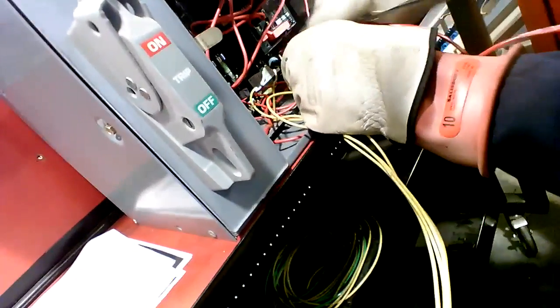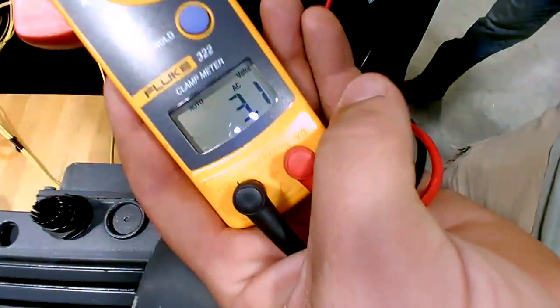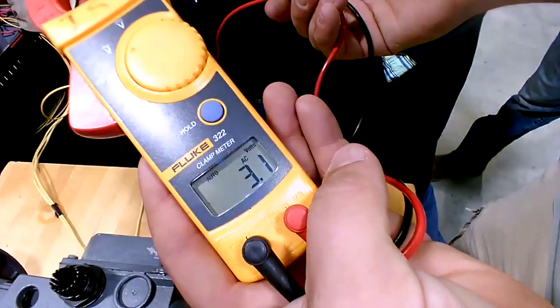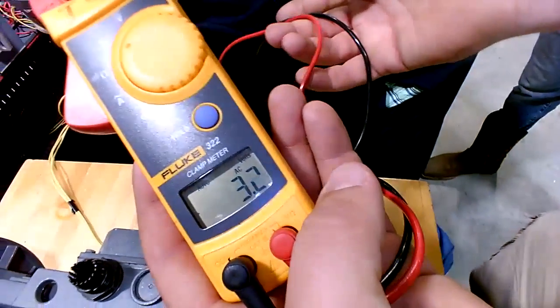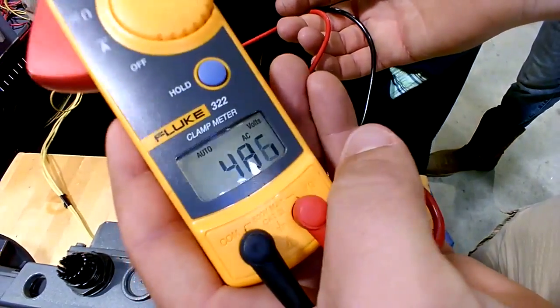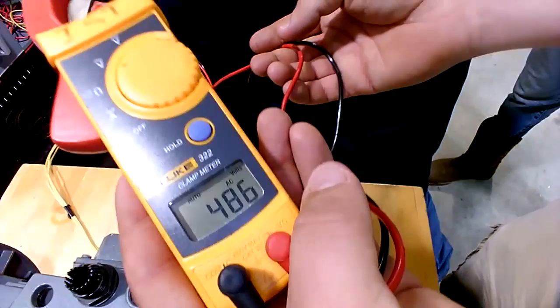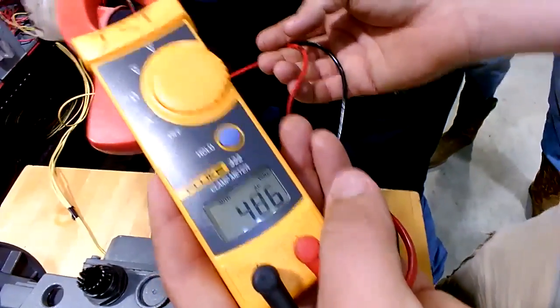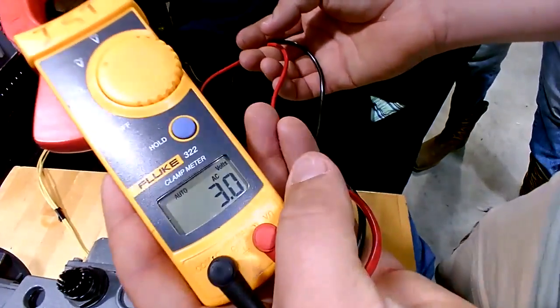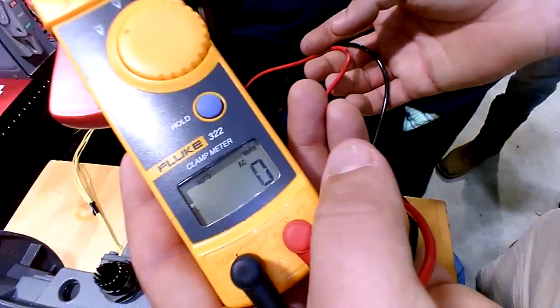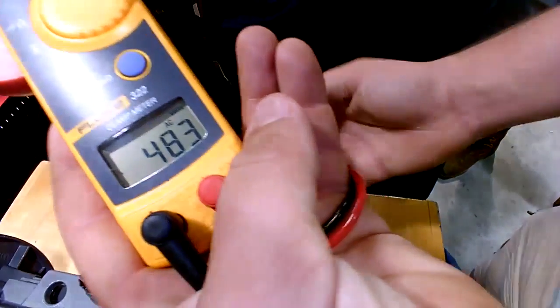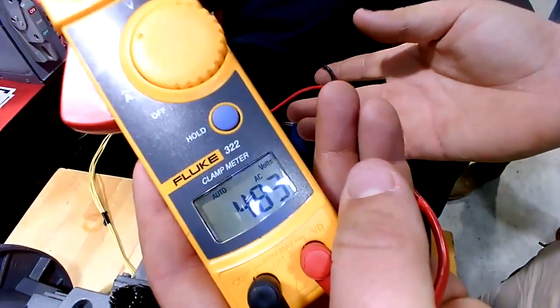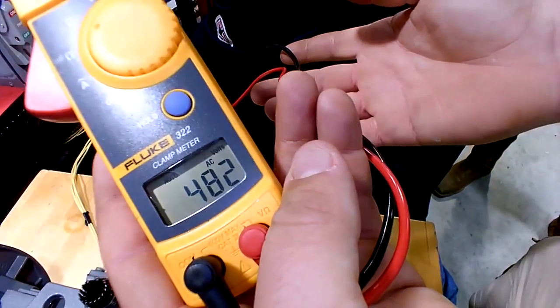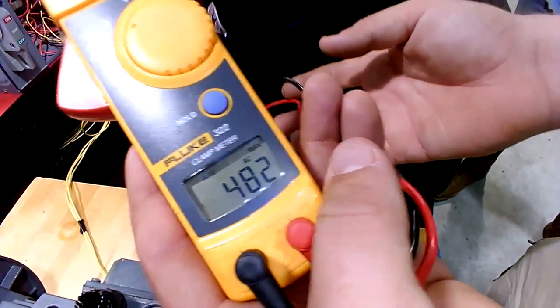I'm going now from T1 to T2. So what voltage are you getting? 3.1. 3.2. Oh, there we go. 486. 486 volts. You got that on the camera? Yep. That's 486 volts. And now I'm going to go from T1 to T3. 483. 482. Now I'm going to go from T2 to T3. 483. 483. The nominal will be 480, but it can be as low as 460. It can be as high as like 490 in that range.